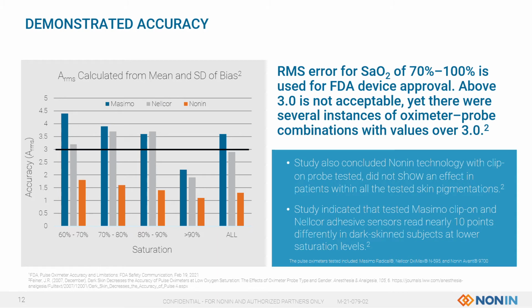So as we mentioned earlier, bias is the mean difference between oximeter reading and co-oximeter. Precision is the standard deviation of differences from co-oximeter measurements. And accuracy, or ARMS, is a standard method for reporting pulse oximeter accuracy, which combines both bias and precision into a simple term. And as we mentioned previously, all three products meet regulatory accuracy ARMS requirements, but they all differ in their bias, precision, and accuracy at different SpO2 levels.